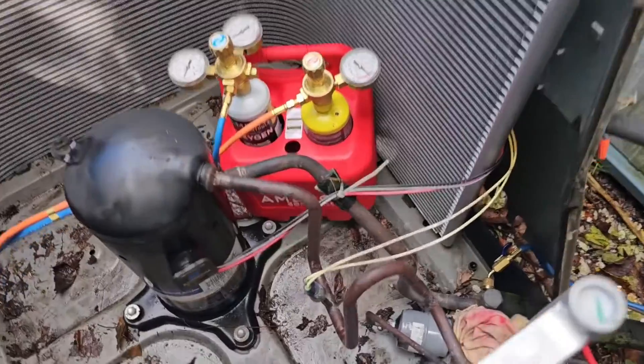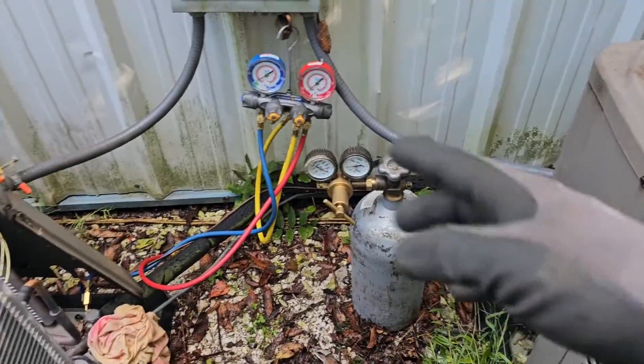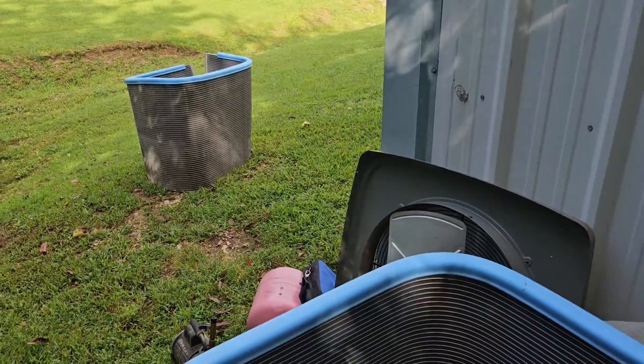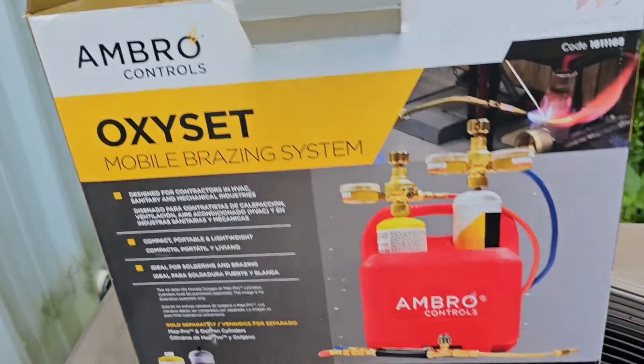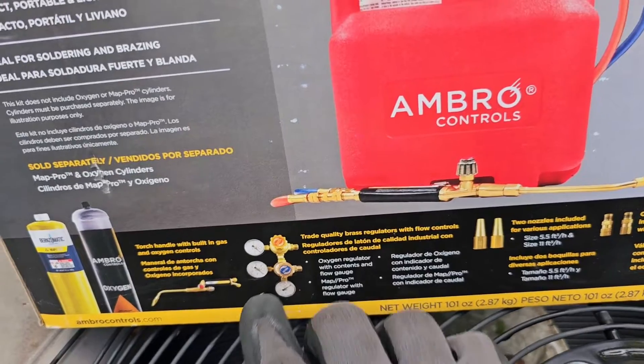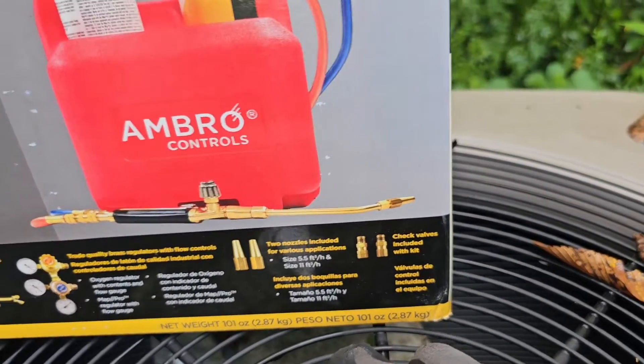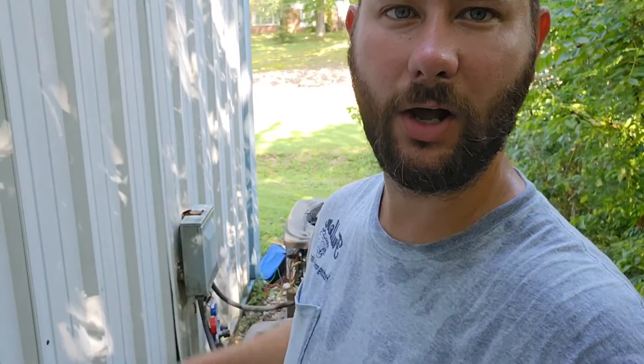And there you have it — Ambro Controls makes a good OxySet. Everything looks good. I'm going to nitrogen pressure test to make sure I don't have any leaks, and that's a job well done. Go check out the OxySet made by Ambro Controls — there's a link in the description. The product comes with a tip, a tank holder, some regulators, a couple different sizes of tip, and some check valves. Super easy to put together. Got the vacuum pump running, got it all put back together. No leaks were found.